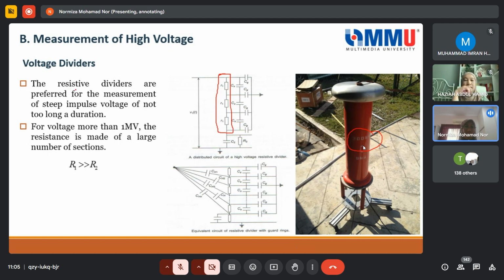So the resistive dividers are preferred for the measurement of steep impulse, and not only impulse, actually, like AC and DC as well. So they divide it into small components for the R1, and then it has the R2 here. R2 can be on its own because of its smaller value. So that's why R2 is much smaller, and it can just be one unit here.